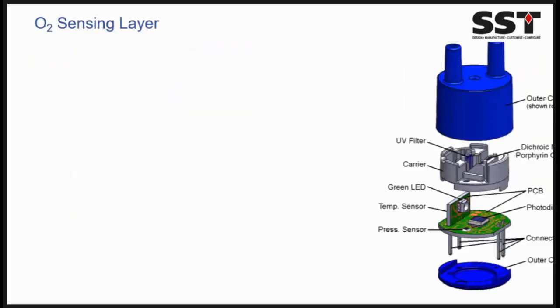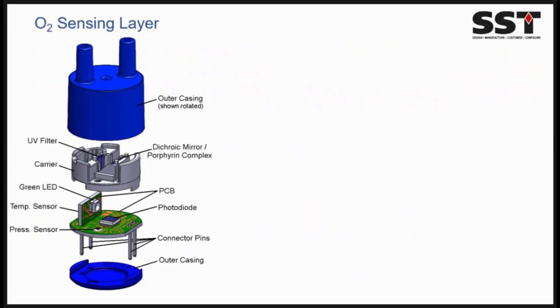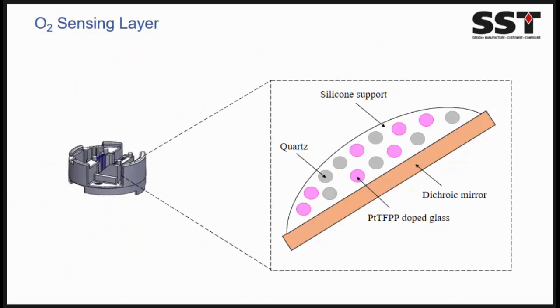So what's the principle? So here's, as you've seen, the part that I've been focusing on. So we have a porphyrin complex that's extremely sensitive to changes with oxygen, but insensitive to other gases. So the way the process works is we immobilize the dye within a glass material, which is then coated with a fluoropolymer that we use. And this is all immobilized within a silicone support. So what we do is we also add in some quartz material for two reasons. Number one is that it enhances the luminescence signal. It causes light scattering. So it bounces the light signal around in the material. And number two, it offers mechanical stability. So the silicone support itself is extremely gas permeable to oxygen, but it's hydrophobic in nature, so it blocks out various other materials.